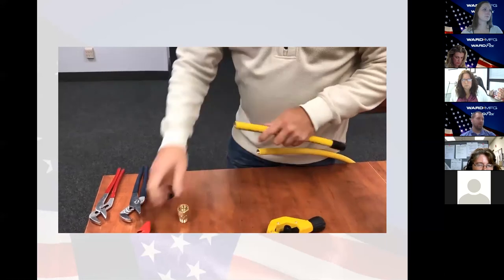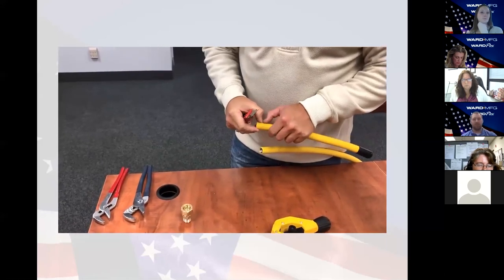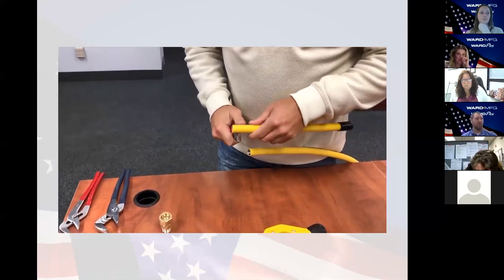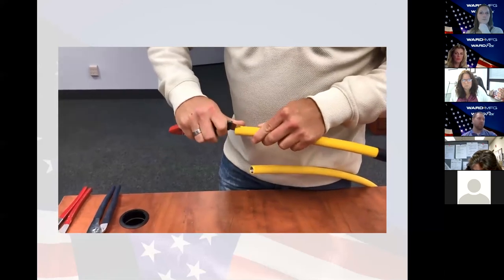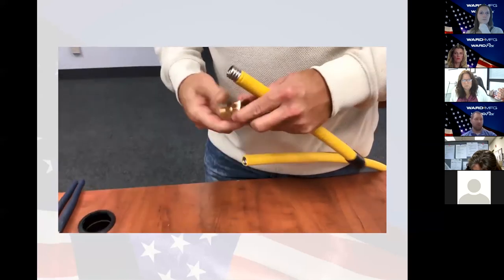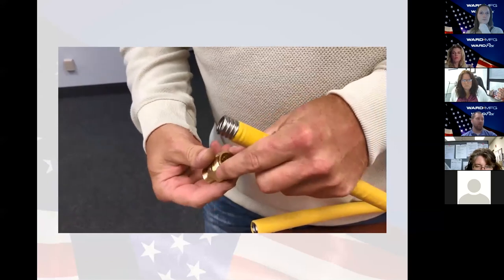The next thing he's going to do is he's going to expose 4 corrugations there. 4 corrugations is our ideal number that allows the coating and the tubing to mate up, and so that there's no exposed stainless. With our WARDFlex MAX coating, we actually specify a maximum of 5 corrugations. So if it's cut back more than 5, it needs to be recut so you shorten that up.